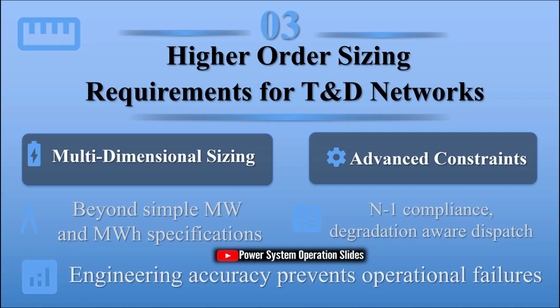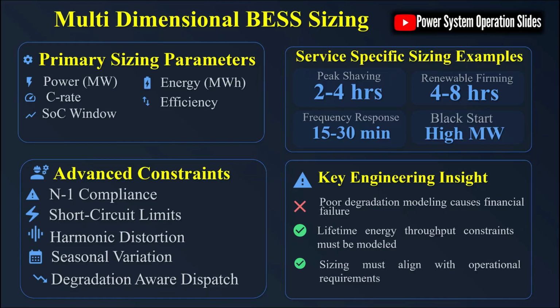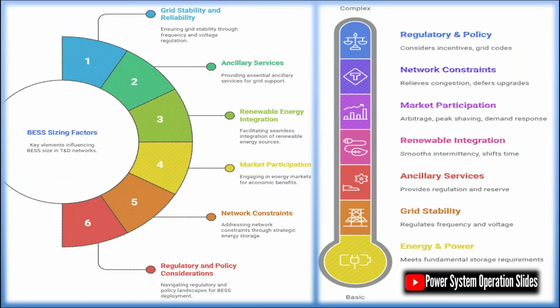Different applications require different sizing strategies. Peak shaving applications typically require 2 to 4 hours of energy capacity, as the BESS must discharge for sufficient duration to shift load from peak to off-peak periods. Renewable firming applications require 4 to 8 hours of energy capacity, as the BESS must smooth variable output over longer time frames to provide dispatchable power. Frequency response applications require relatively low energy capacity, typically 15 to 30 minutes, since the response is brief but requires high power output. Black start applications require high power output but relatively low energy capacity, as the BESS must provide sufficient power to restart generation resources but does not need to operate for extended periods.